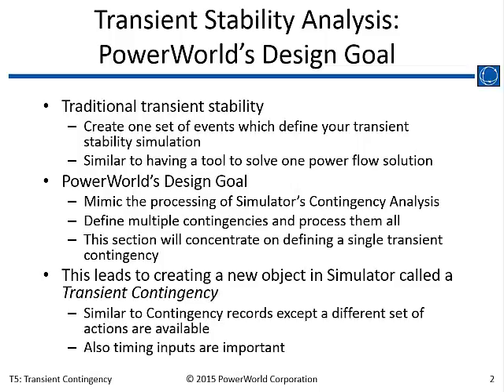We designed the transient stability tool within Simulator to be more flexible by mimicking what we do with the power flow contingency tool. We allow you to define as many contingencies as you want and process them in sequence — one at a time — getting a series of results. There's now a new object called the transient contingency; power flow contingencies and transient contingencies are distinct objects, so you can't define one and expect to use it in both tools.